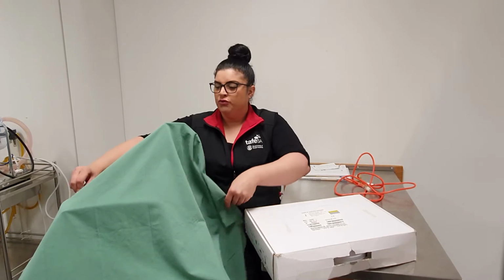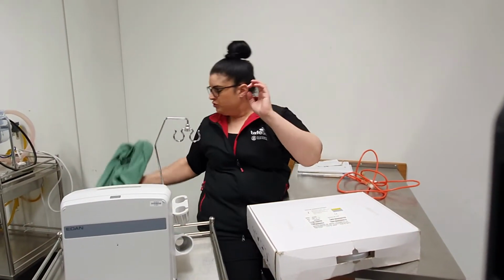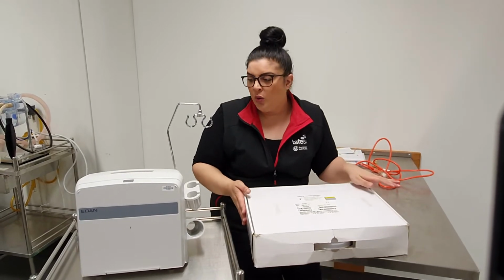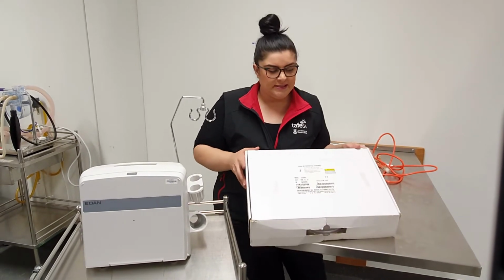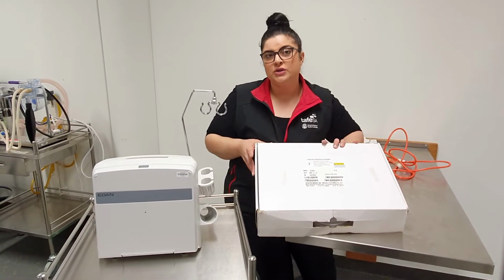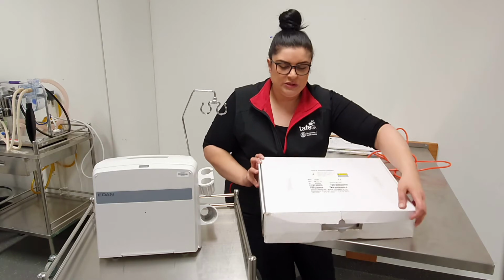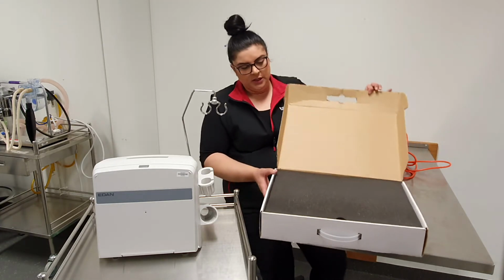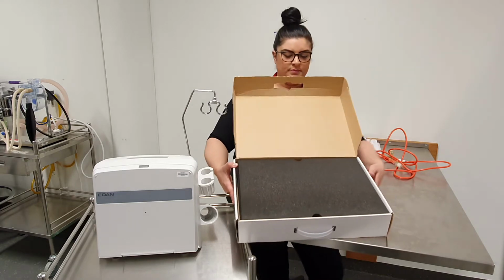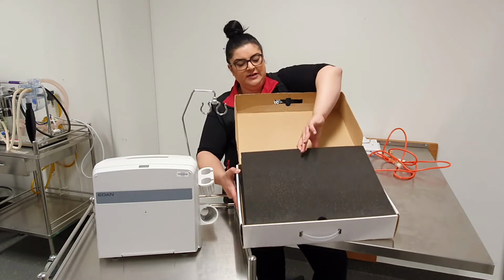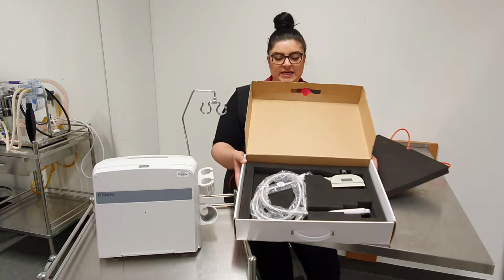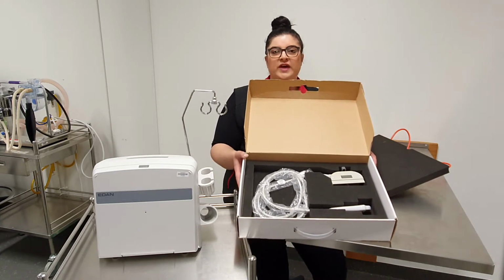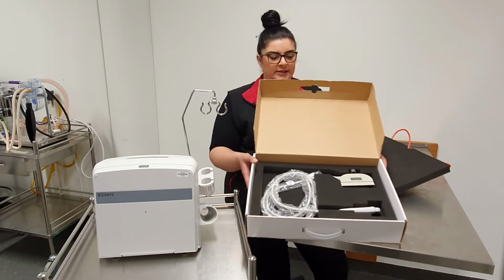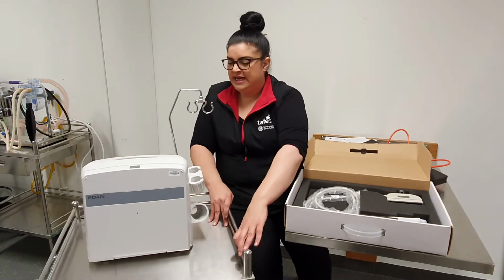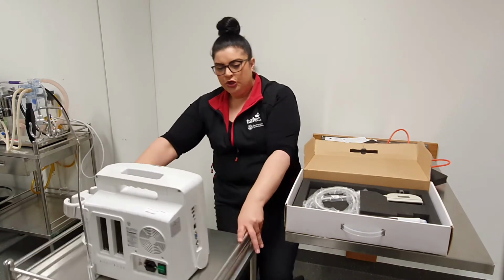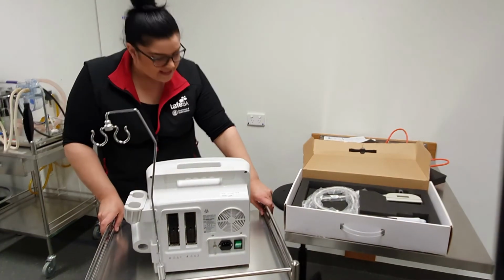Okay, so I am going to remove the dust cloth from our ultrasound machine. Now, with the probes or the transducers, again, if you do have the padded box that they came in, that is the ideal place to store them, and I'll show you why. You can see here I've got a piece of foam on top of the transducer, and when I lift the piece of foam, it's sitting in there nicely, nice and safe, and we just store that on the shelf at the bottom of the ultrasound machine. Now I'm going to turn the ultrasound machine around and show you the back of it so that we can talk about how we set this up.